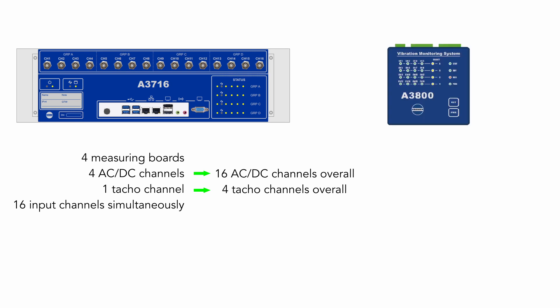Second one is online unit A3800. The difference between these units is in number of measuring boards. This unit has only one board and by default it can measure four AC channels, four DC channels and one tacho channel. But it can be extended to version where you can use also 16 AC channels, 16 DC channels and four tacho channels. This is configured with a license.